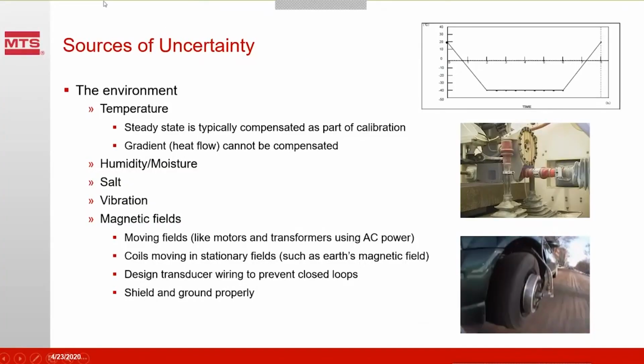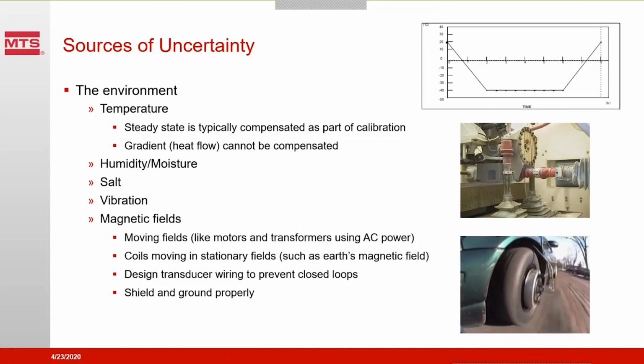What are other sources of uncertainty in our environment? Well, temperature, of course, I mentioned that several times. It's probably the single biggest change factor for transducers and accuracy of measurements. Steady state is easy to compensate. We can soak things in ovens at steady state temperatures, and we can apply resistors or compensation techniques to linearize or flatten that curve so it's not very sensitive to temperature.